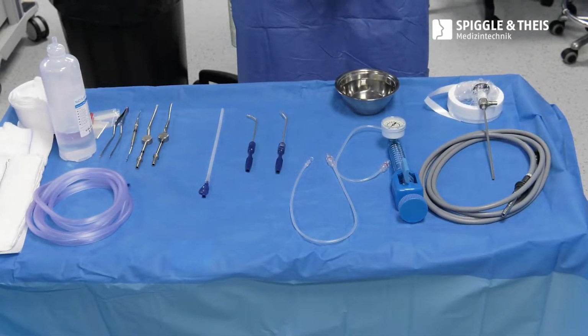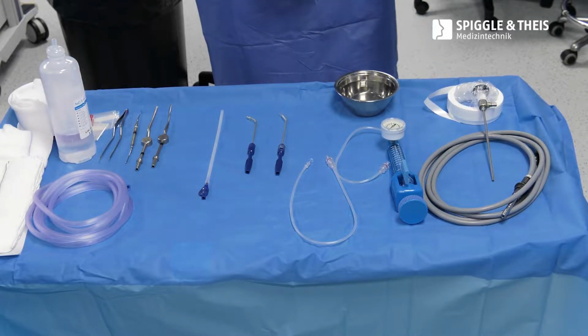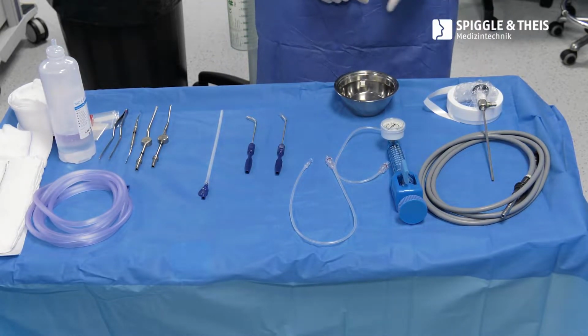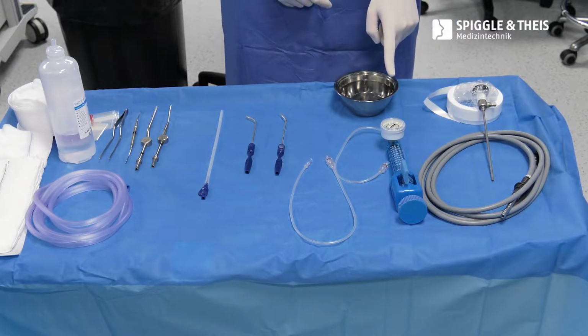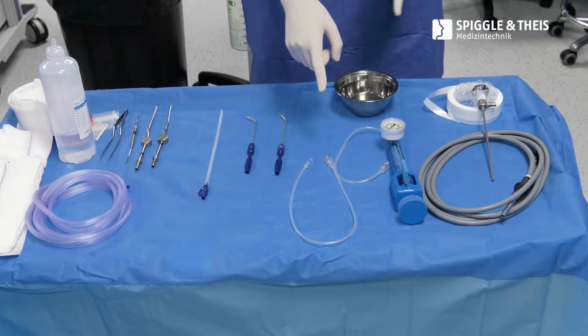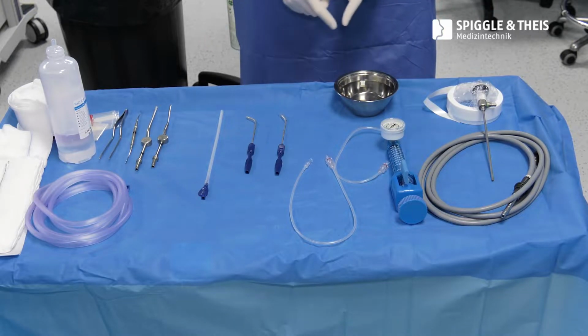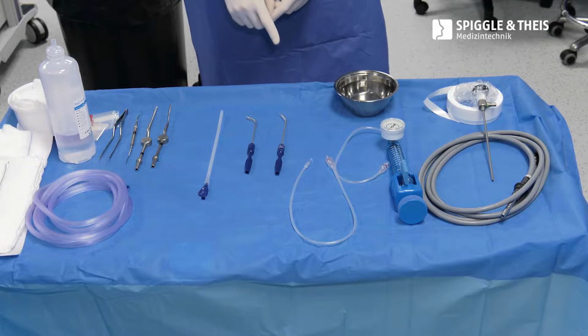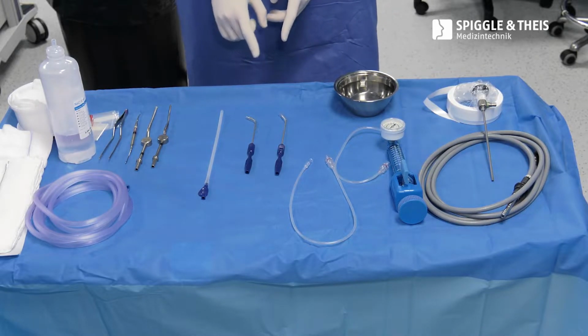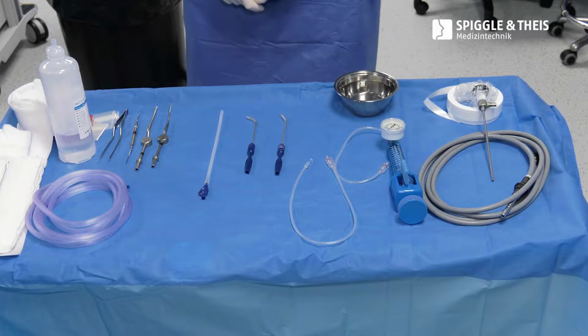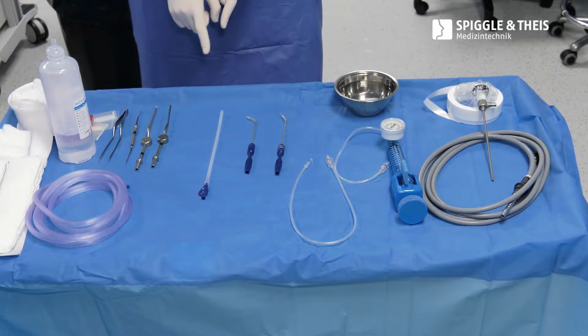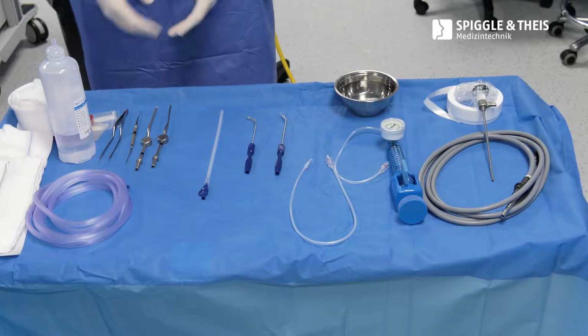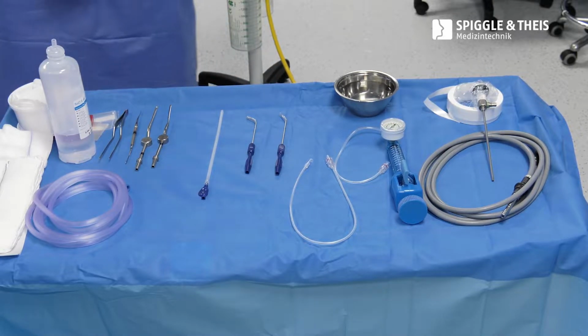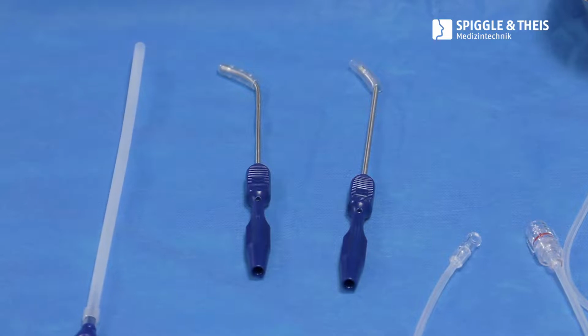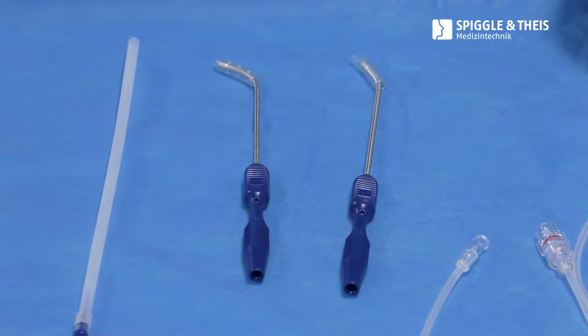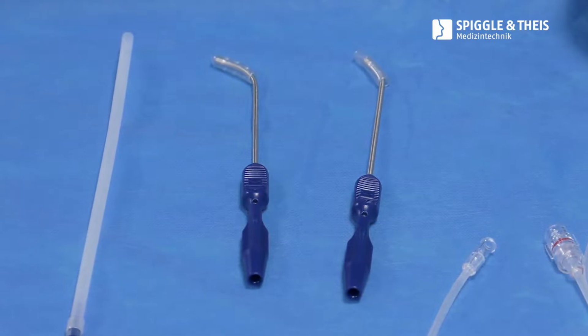We will first describe the materials needed to perform this procedure: nasal endoscope of 0 or 30 degrees, physiological saline solution, inflation pump for inflating and controlling the pressure inside the balloon, extension tube, angled insertion instruments through which the catheter will be introduced into the Eustachian tube, Tubavent balloon catheter, nasal suction tubes, a bayonet nasal forceps, and a nasal speculum. We will usually use insertion instruments with angles of 45 or 60 degrees on adult patients.